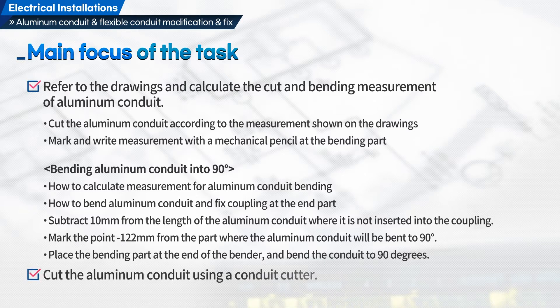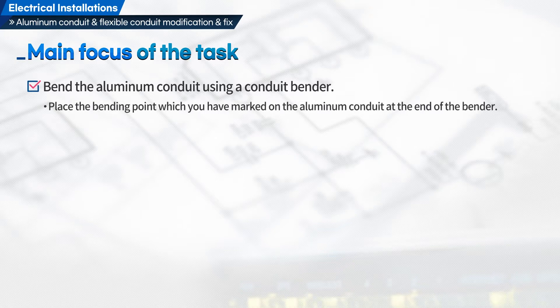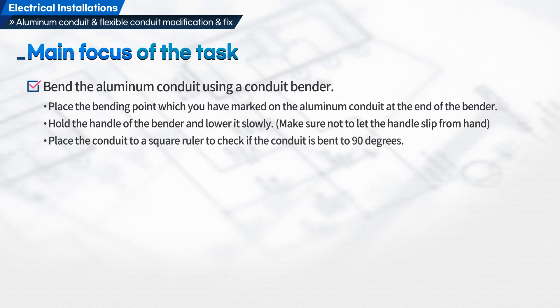Second, cut the aluminum conduit using a conduit cutter. Third, bend the aluminum conduit using a conduit bender. Place the bending point which you have marked on the aluminum conduit at the end of the bender. Hold the handle of the bender and lower it slowly. Make sure not to let the handle slip from your hand. Place the conduit against a square ruler to check if the conduit is bent to 90 degrees.